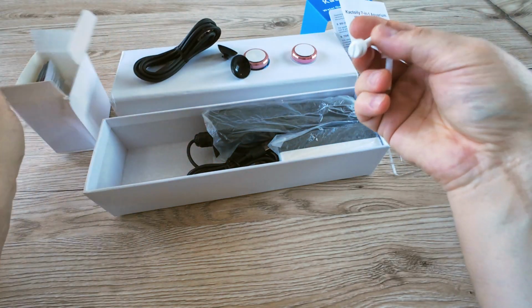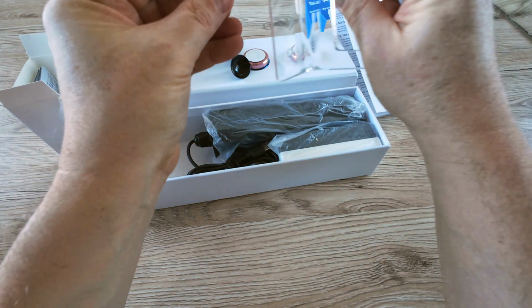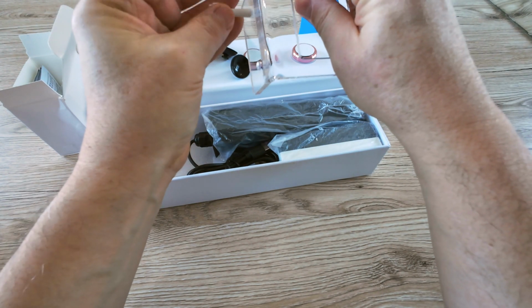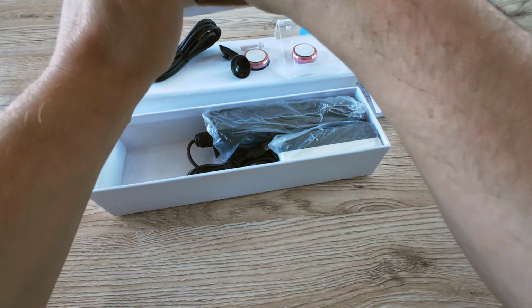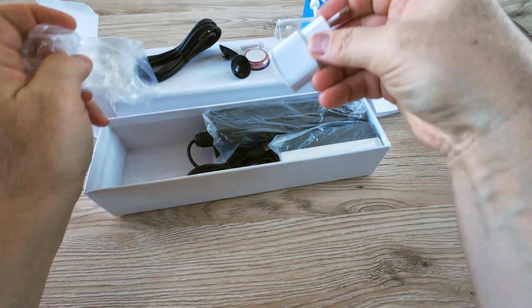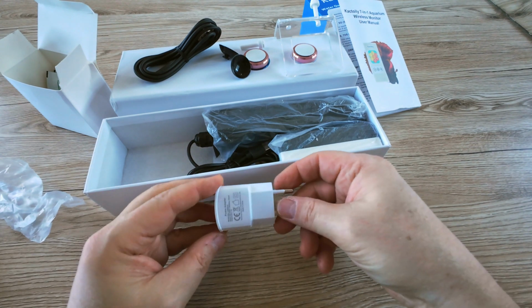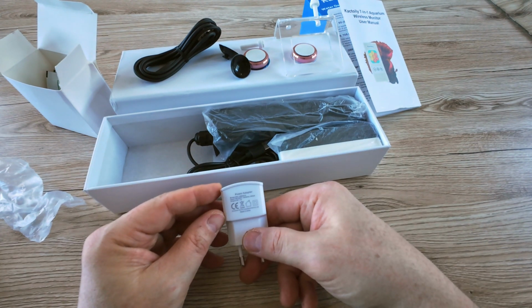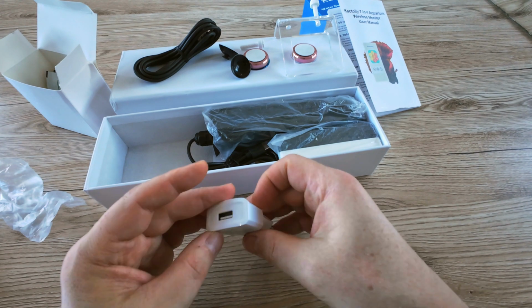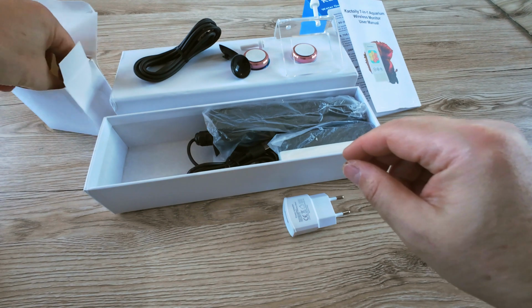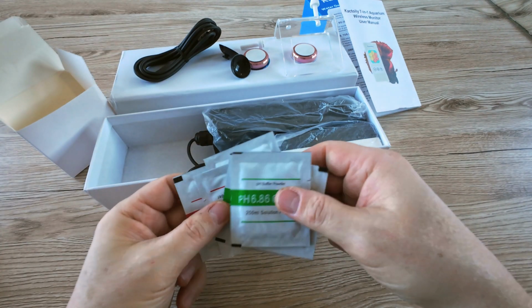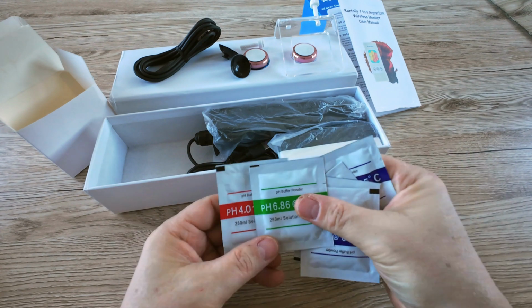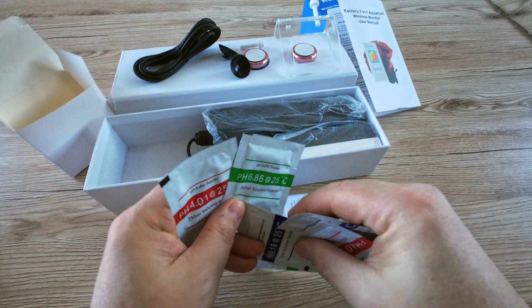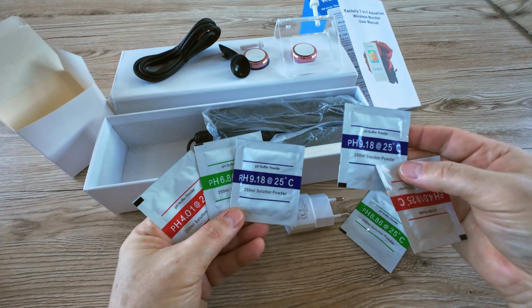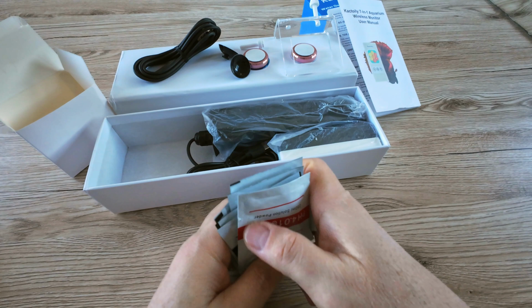Next we have two plastic screws that go into this holder for attaching it to the edge of the aquarium or something. Then there are chargers. There is one more in the box. Then here are two sets of calibration powders that you dissolve in RO DI water to calibrate the pH probe. We've got a standard for pH 4.01, 6.8 and 9.18. Well, that's fine.